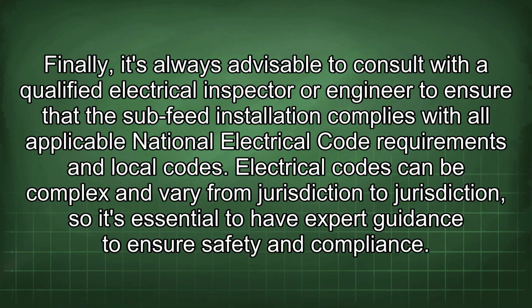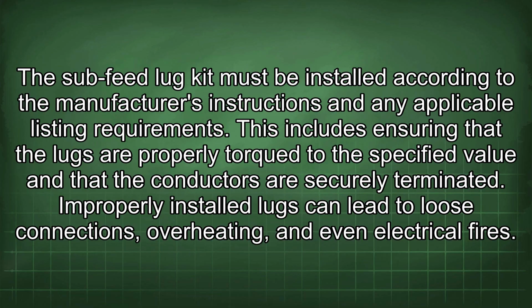Finally, it's always advisable to consult with a qualified electrical inspector or engineer to ensure that the sub-feed installation complies with all applicable National Electrical Code requirements and local codes. Electrical codes can be complex and vary from jurisdiction to jurisdiction, so it's essential to have expert guidance to ensure safety and compliance. The sub-feed lug kit must be installed according to the manufacturer's instructions and any applicable listing requirements. This includes ensuring that the lugs are properly torqued to the specified value and that the conductors are securely terminated. Improperly installed lugs can lead to loose connections, overheating, and even electrical fires.